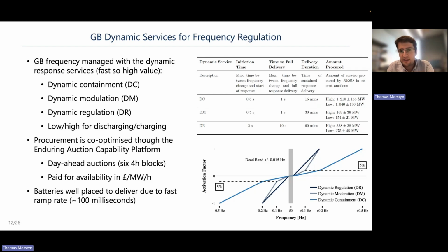So dynamic containment is the fastest one. You have to deliver it within 1 second, and you have to be able to sustain power delivery for 15 minutes. On the other hand, dynamic regulation is slower. You have to deliver it within 10 seconds, and then it has to be sustained for up to 60 minutes. And each of these has a low and a high variant. The low frequency variant is discharging the battery, whereas the high frequency variant occurs when there's too much supply in the system and you're actually paid for charging your battery.